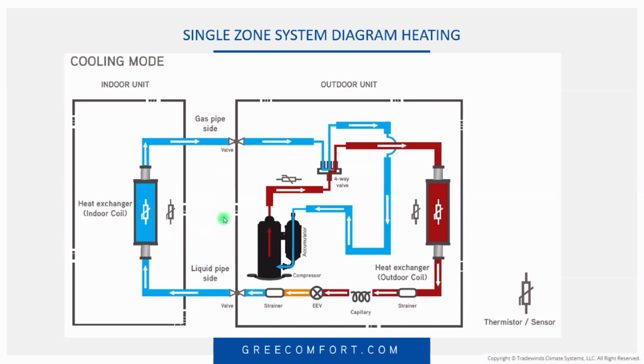So I want to talk a little bit more about your line sets with mini splits. You've got your liquid pipe and your gas pipe. A lot of people want to call that the suction liquid line. Well, essentially, yes, it is the suction line if it's in cooling mode. But if it's in heating mode, it is the discharge line. Daniel has talked about it before. When we're down here, I'm going to talk about it again.